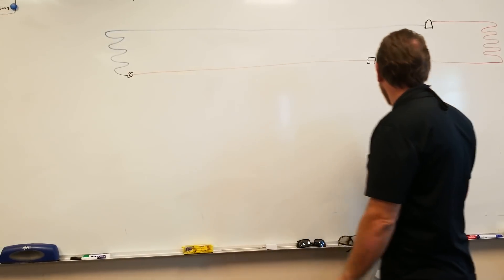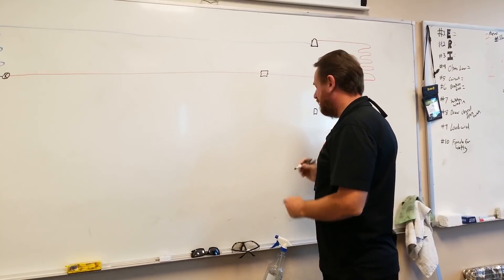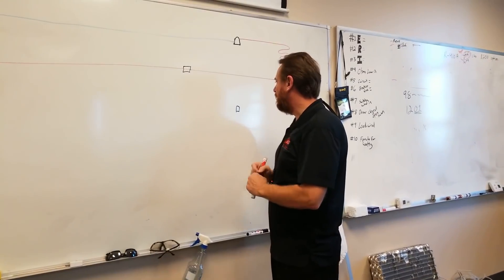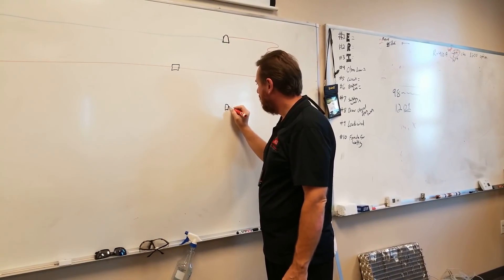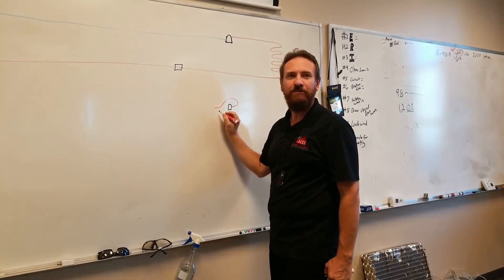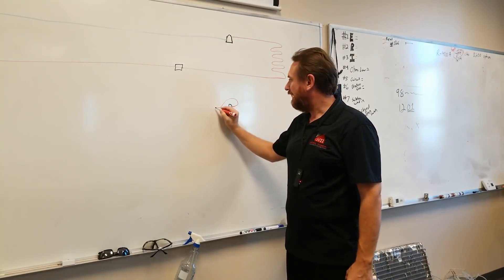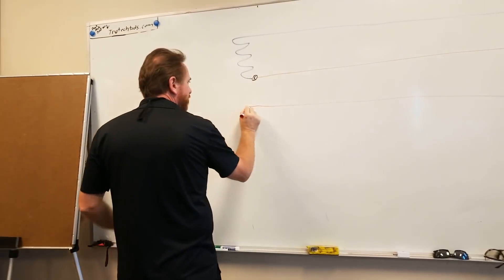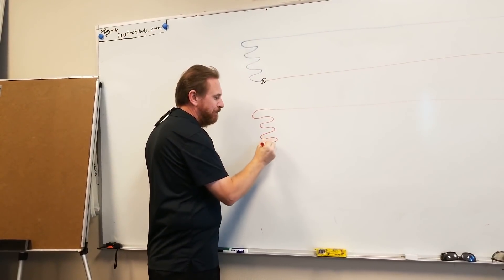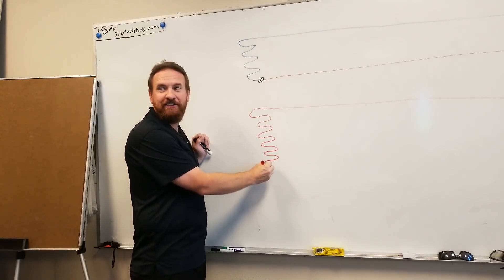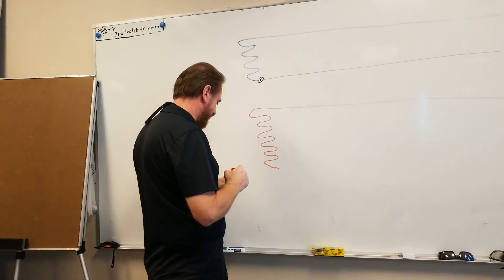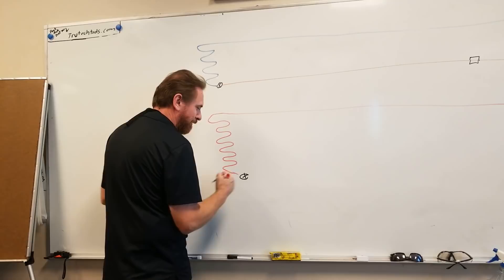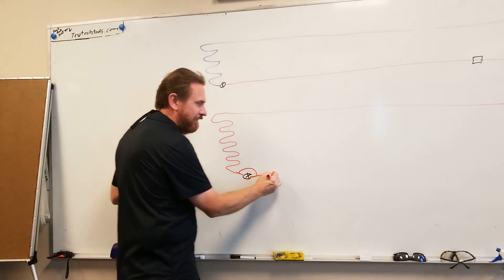Now if I took this very same compressor and all I did was swap the pipes — the compressor still pumps only in one direction — but if I took those pipes and switched them so that the discharge pipe went over here and connected to what was the suction gas line, and started pumping my refrigerant this way. My refrigerant would de-superheat, change from a vapor back to a liquid, and then sub-cool that liquid inside. And if I took this metering device and bypassed it — just put a little bypass around it.